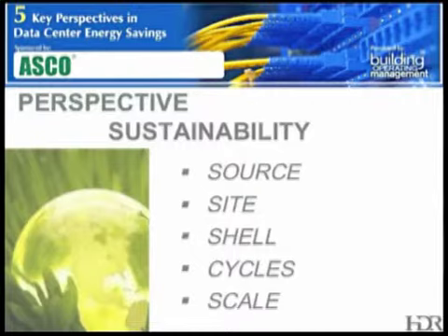The shell of the building is absolutely critical as well, and this is probably best understood in terms of energy reduction in construction techniques. Certainly don't design by the table. It's not a one-size-fits-all. You must look at that particular environment that you're located in and the building type specifically that you're looking at. It's not always just a building with data components in it. There's often a lot of program around that, or this is one component of a larger facility.